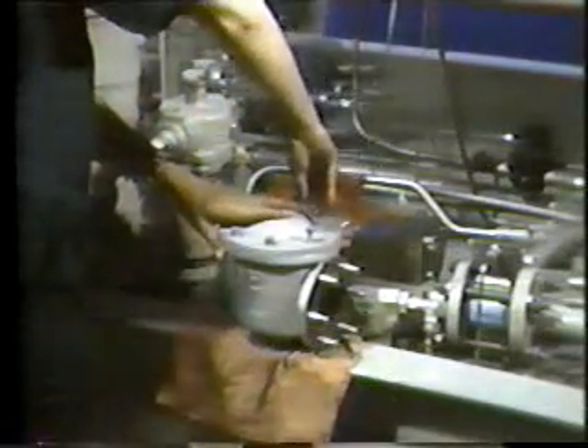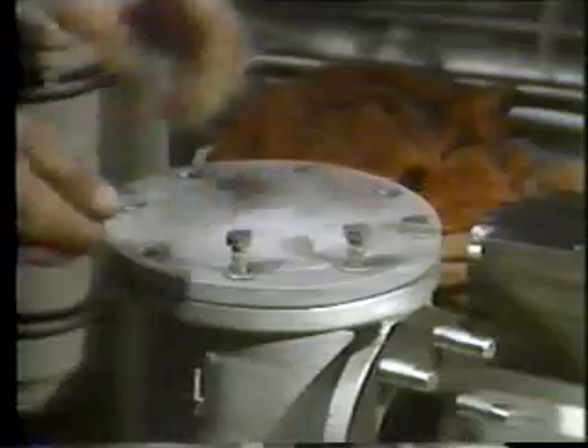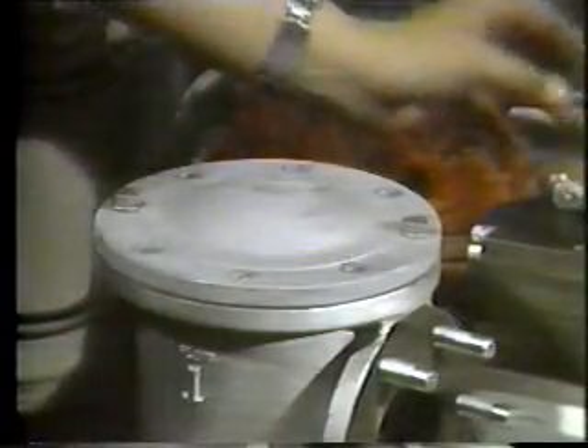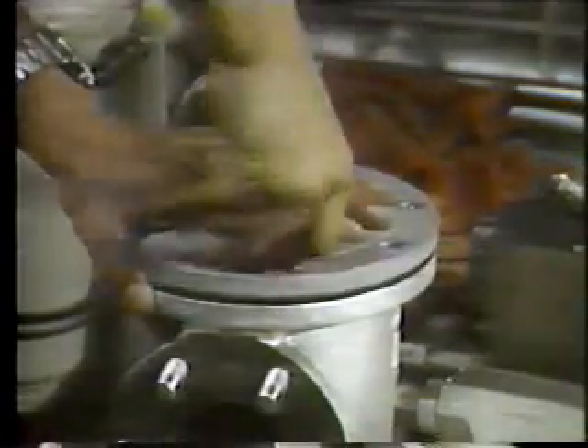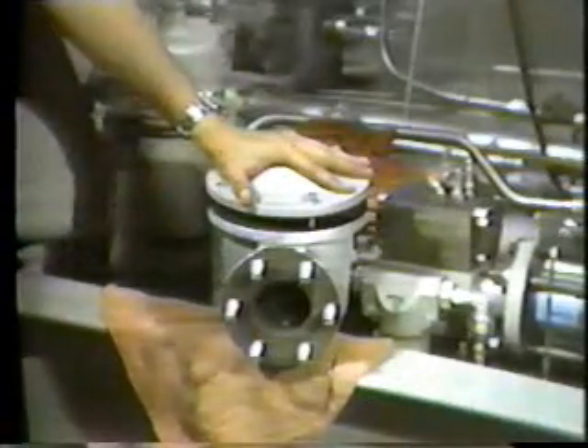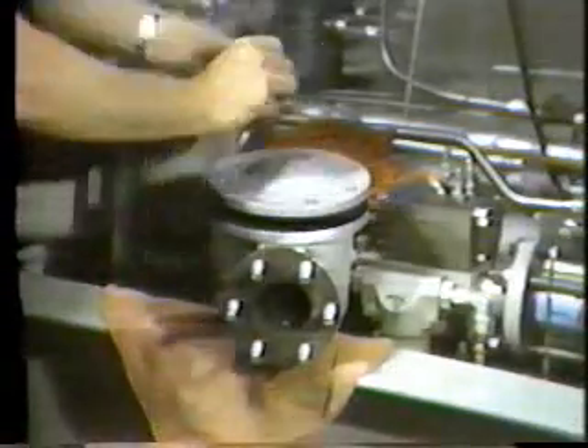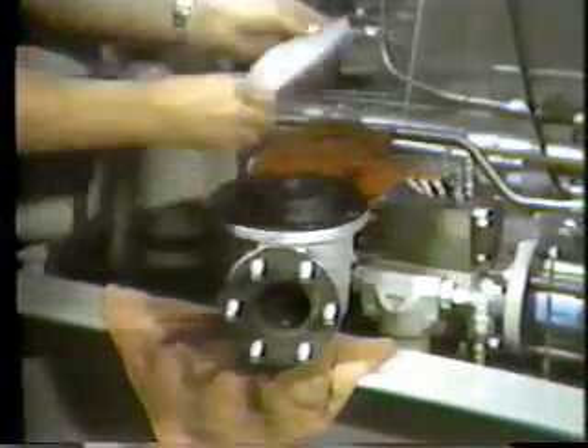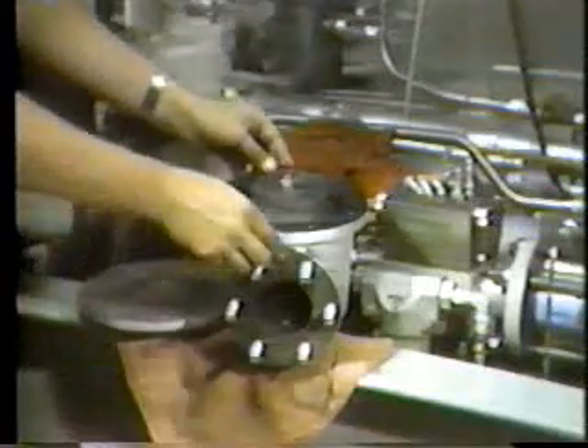Warning: be careful while removing the cover in the next step. There is a spring inside that can possibly fly out and injure you. Remove 6 of the bleed valve cover bolts. Place one hand over the cover to overcome spring tension. Then remove the last 2 bolts. Remove the cover gasket and discard it.